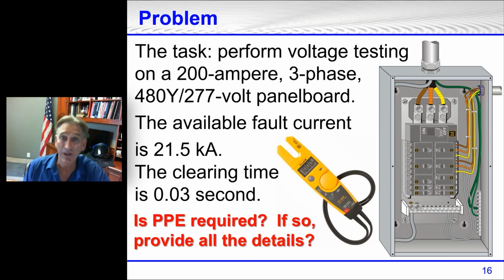And they'll look at me like, what? Because my question is, what are the required colors in accordance with the National Electrical Code? These are industry standard colors. Everywhere you go in the US is not going to have these colors. Now, the National Electrical Code does have some colors that are required, like if it's a 3-phase 4-wire delta high leg system, that high leg has to be color coded orange. There are other colors that are used out there.